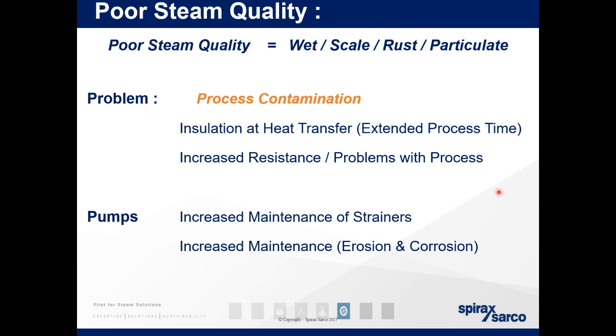So this says that if you have any insulation in the pipe between the steam and what you're heating, that could be from air, or it could be from scale, it could be from burnt product. It's going to extend the process time, how long it takes to heat the media you're trying to heat. Increased resistance, problems in process. So again, if temperature is very important in your process, say it's a cooking process where you need to maintain a certain temperature, I could think that would probably be in the milk industry in particular as well.